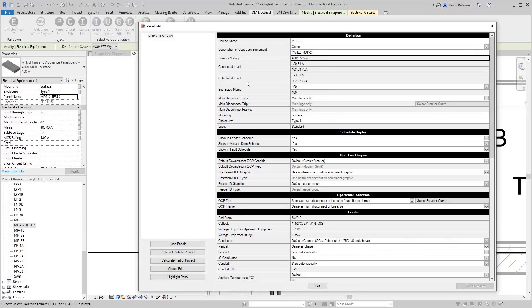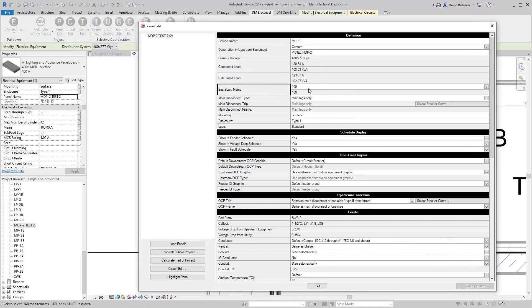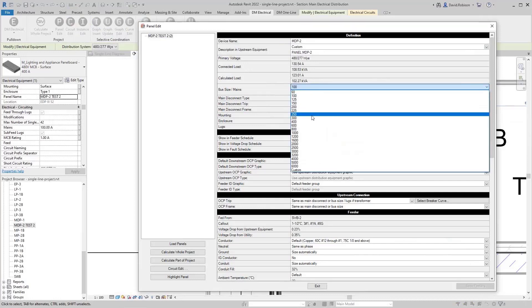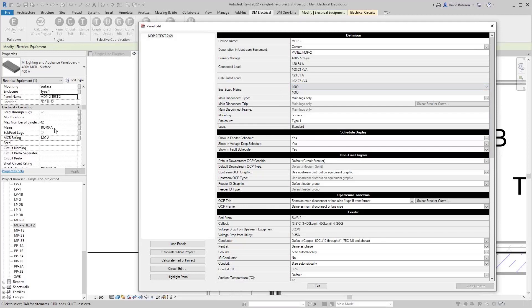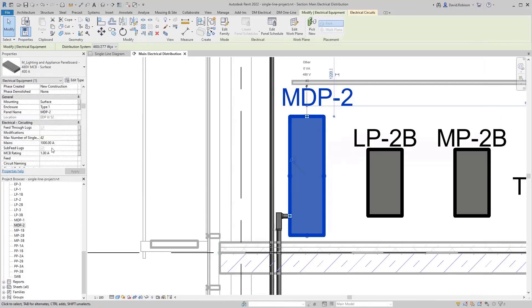The next values pull information from Revit for informational purposes — we show you the voltage, the connected load, and the calculated load from Revit so you know what Revit is seeing as loads on the panel. You can then use that to choose your panel size, which we call bus size (Revit calls it mains). We list both names. You can set a custom size if the default options don't fit, or type in whatever you need.